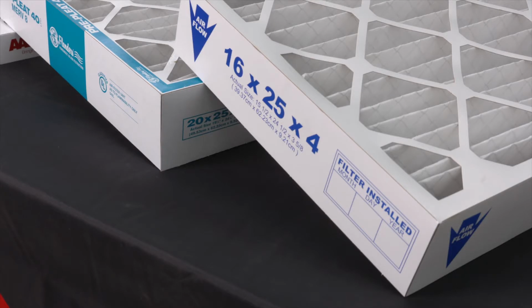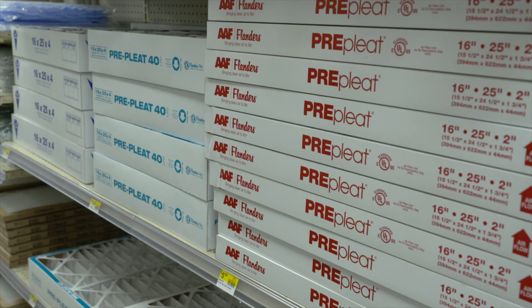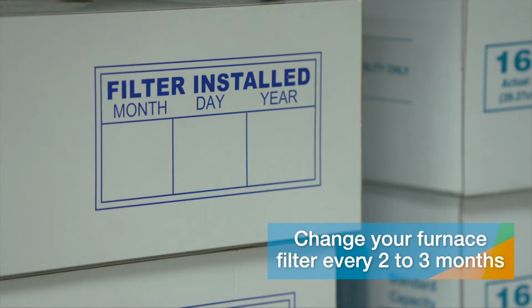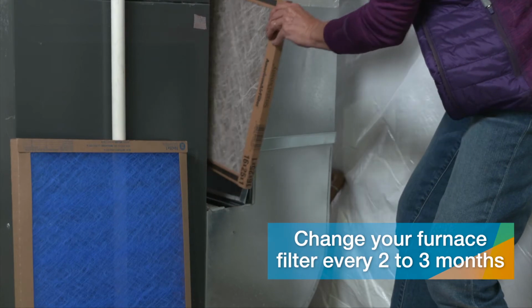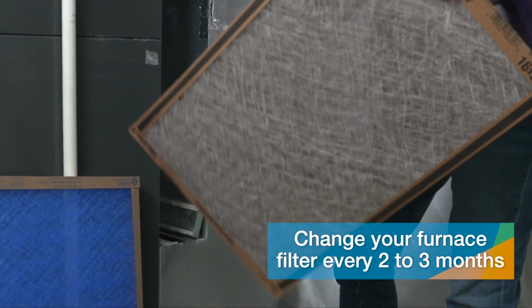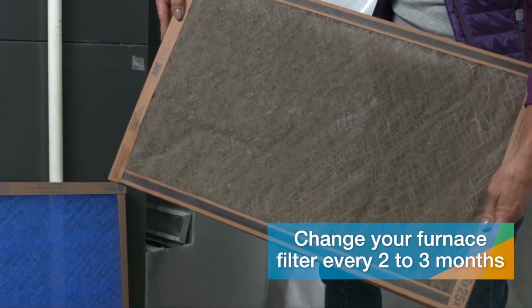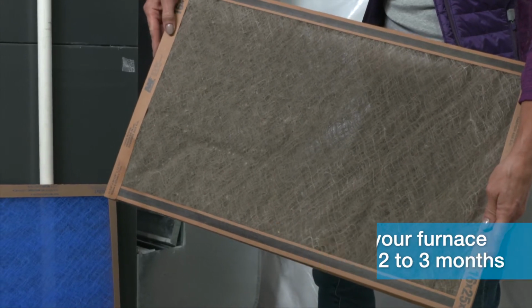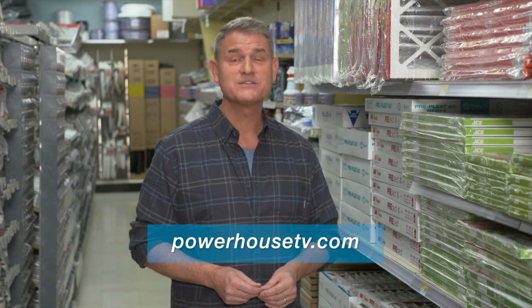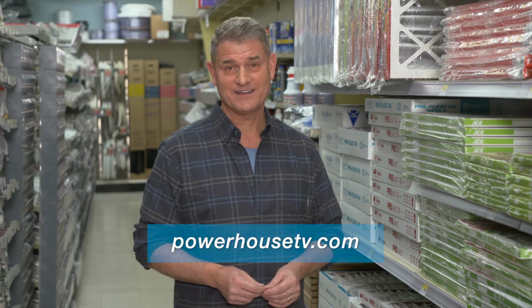Now, too high a MERV rating in your residential system could actually starve your system for air and cause the high efficiency components of your furnace to actually be less efficient. No matter which filter price point you choose, the important thing is to change it every 2 to 3 months. When you do, you should be able to tell how it's performing by what it's collecting, as well as if it's operating efficiently with the system. If you need additional information about filters or other HVAC tips and tricks, be sure to visit PowerHouseTV.com.